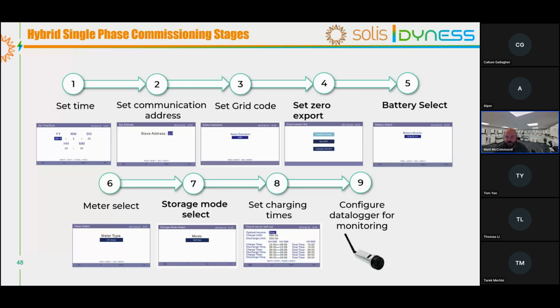Set the export if you need it. So if you want to change the backflow power, so for example, you had a 5 kilowatt inverter, but the DNO have come back and said you're only allowed to export 4 kilowatts, then you can actually set the backflow power. Because we already have the meter in place, that's where that information came from, and then we can do it directly off that and then set it up. Our inverters are G100, so you should be no issues in terms of applying to the grid for that.